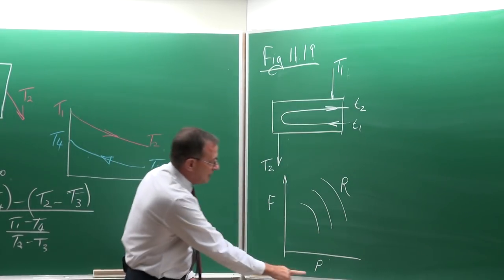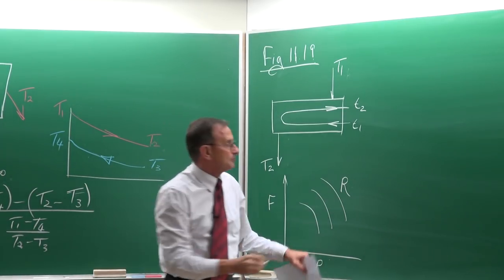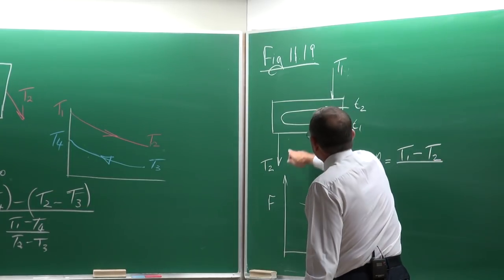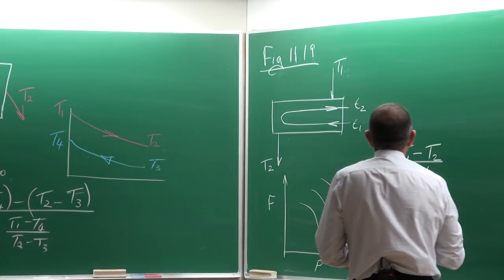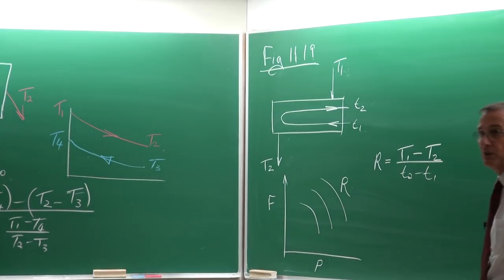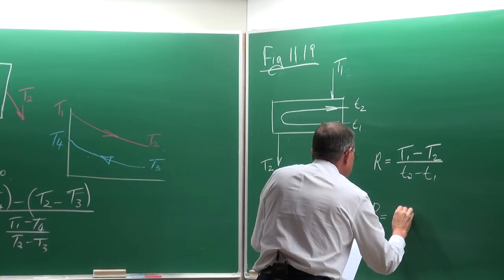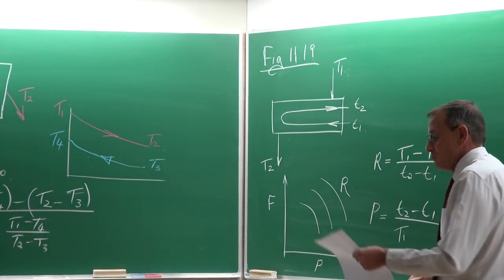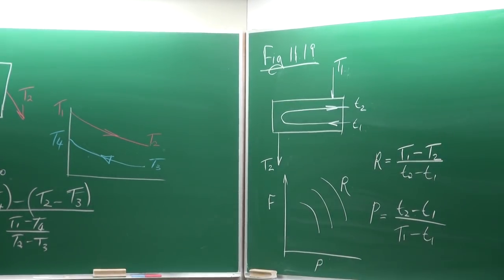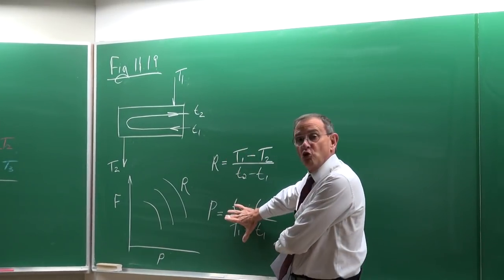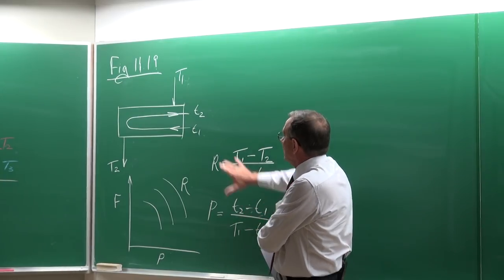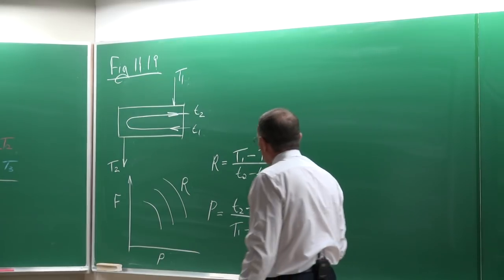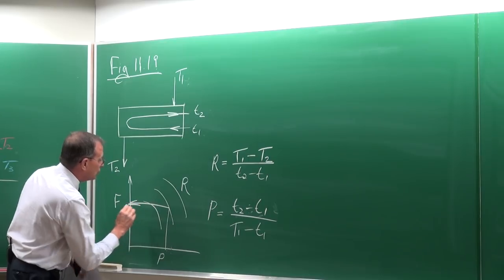Just go and look at the sketch and the graph — the graph shows the values of P and R. For this specific case, R equals capital T1 minus T2, divided by lowercase t2 minus t1 (outlet minus inlet temperature of the tube side). P equals lowercase t2 minus t1, divided by capital T1 minus lowercase t1. Once you have P and R, it is very easy to read off the correction factor from the graph.